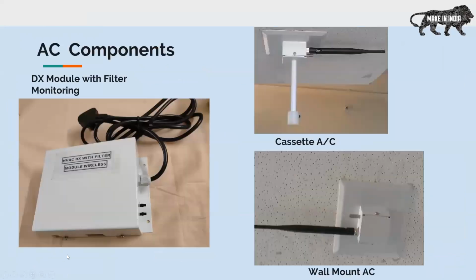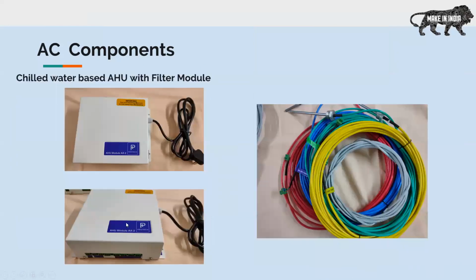Then this is the DX module, where these two ports provide for sensors for supply air and return air, then your unit status, unit control, filter monitoring, and external. These two are for IR-based modules for controlling IR-based units such as splits, cassettes, and towers. Now the module being shown here is for the chilled water AHU. On the right-hand side you have four ports in blue. This is for return air temperature, this is for supply air temperature, this is for chilled water supply, and chilled water return. On the left-hand side is for actuator control and feedback and VFD control.